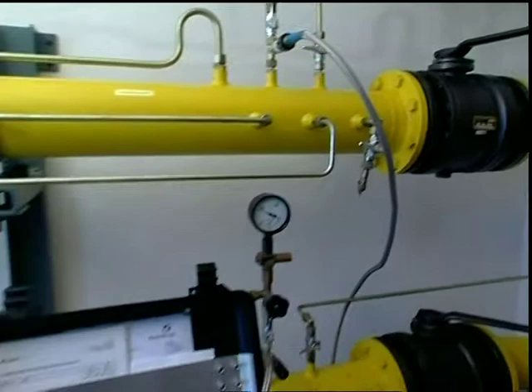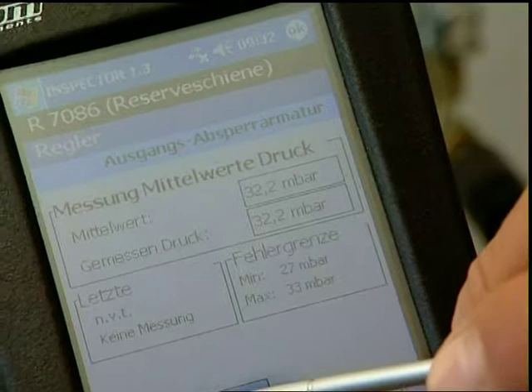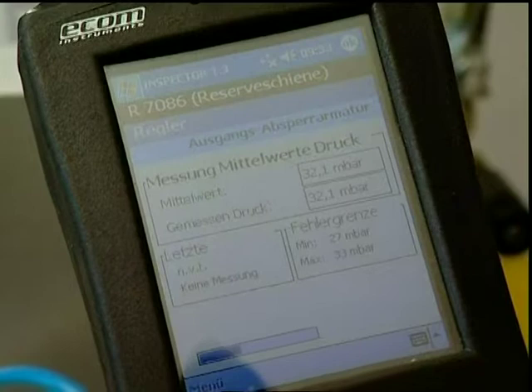The test begins with the function test of the pressure regulator. The flow pressure of the regulator is simulated by opening the vent. The pressure values can be read directly in the display of the PDA. The succession of the gate time areas is presented in the display of the PDA. At the end of the measuring cycle, storage of the data takes place. If the measured values are outside the allowed tolerances, a message appears in the display immediately.